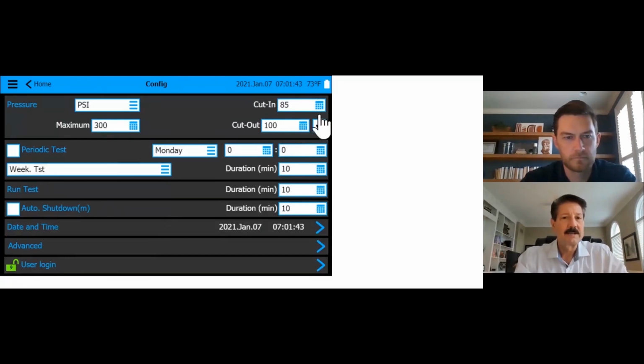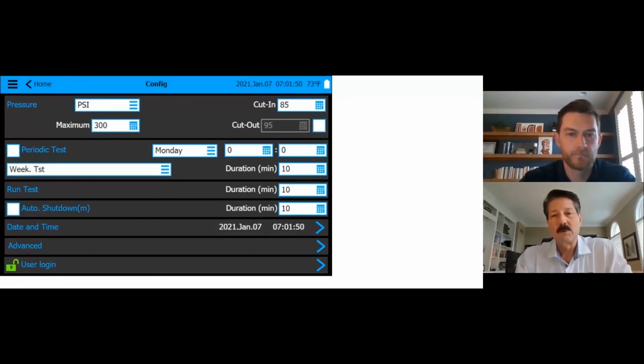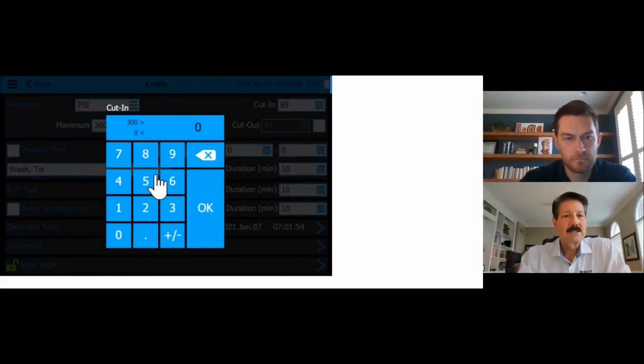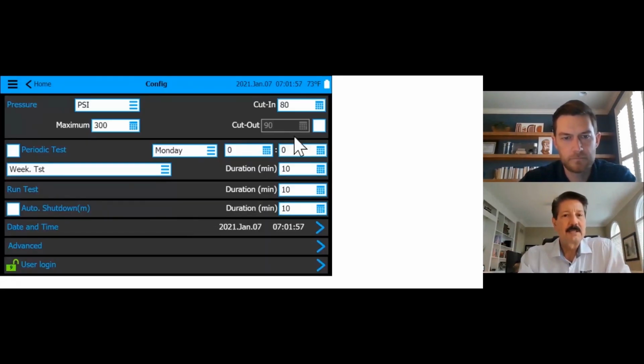One little feature here is we have the option of automatically putting it 10 PSI. So if you want to do one less keystroke, whatever your cut-in pressure is set at, in this case, I'll lower it to 80. You see, it automatically puts the cutout at 10 PSI more. On a manual shutdown, it doesn't matter really if the cutout is 1 PSI, 5 PSI, 10 PSI above the cut-in, because it manually has to be shut down. The only time it really is critical is when you have an automatic shutdown.